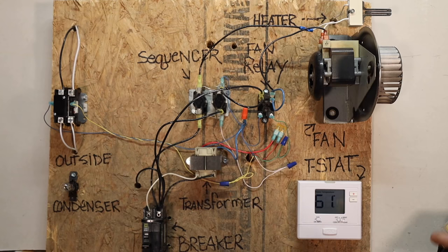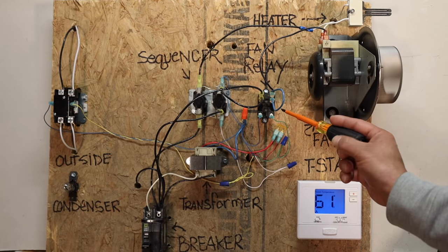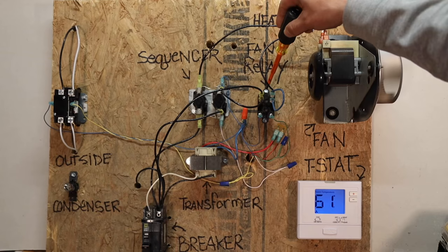Okay, I'm going to give you an example of that. Fan on. So right now, power is being passed from here through the piece of bimetal, which has made a closed circuit now on the top spade clips and turned on your blower motor.